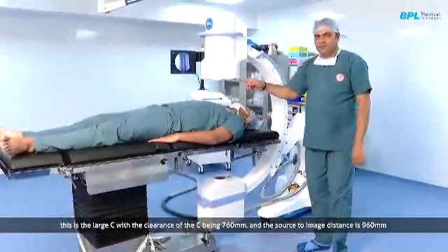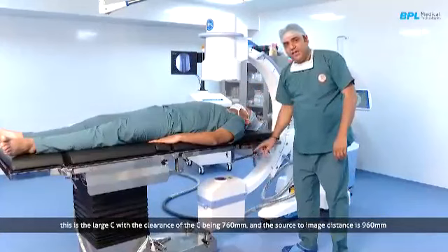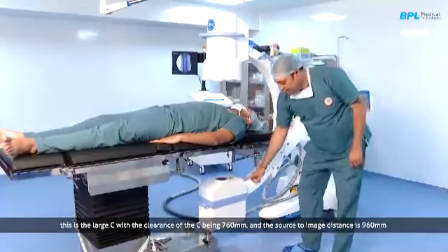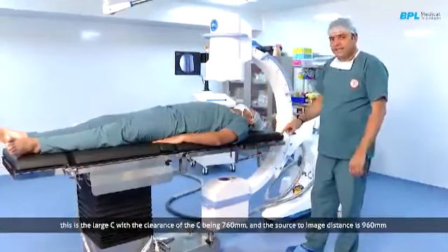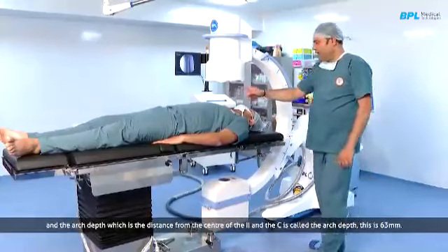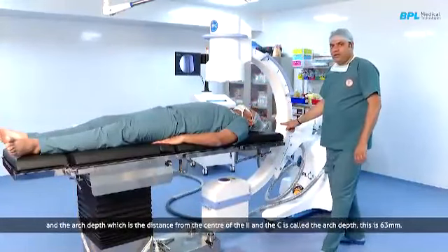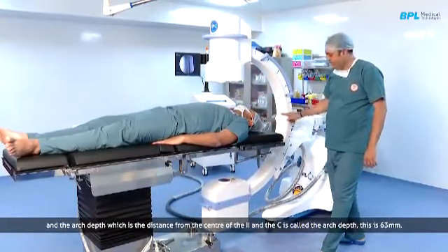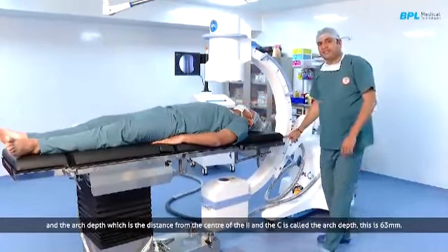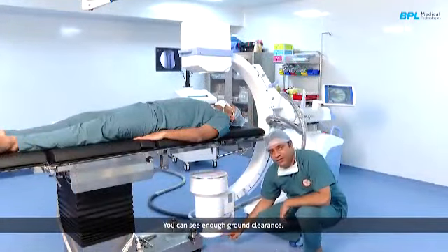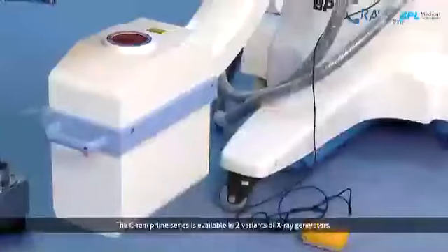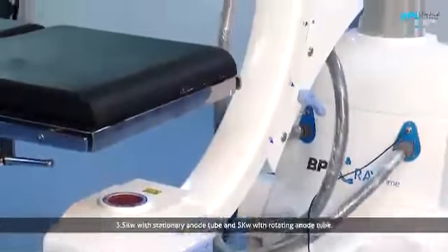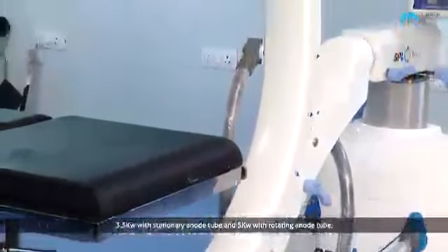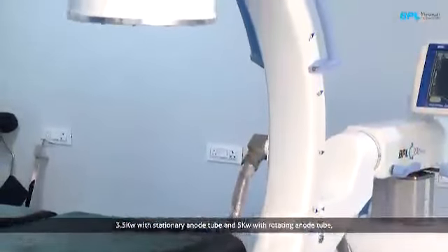The clearance of the C is 760 mm, and the source to image distance is 960 mm. And the arc depth is center of this II to the center of this C is called arc depth. This is 63 mm. So you can see the enough ground clearance is there. C-Ray Prime series is available in 2 variants of X-ray generator. One is 3.5 kilowatt with the stationary anode tube, and other is 5 kilowatt with rotating anode tube.